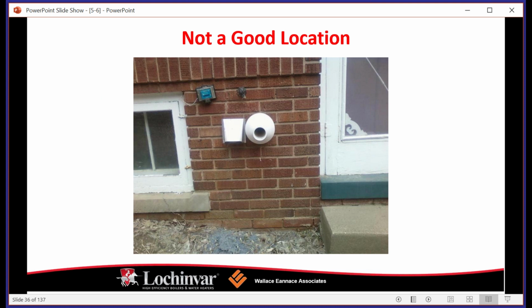For one thing, we are expelling flue gases, and those flue gases do contain carbon monoxide. So you want to make sure that you're not directly adjacent to a fresh air intake, say a window or a door. We have basically a window and a door within what looks to be about a foot of our flue gases, so that's a bad idea.